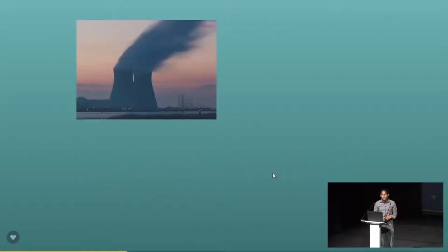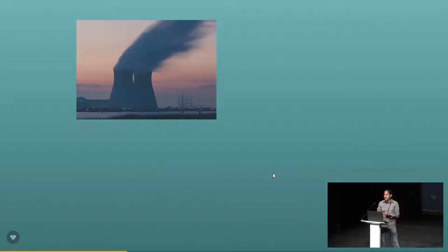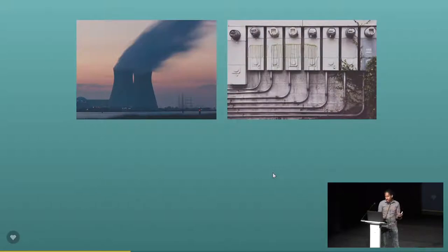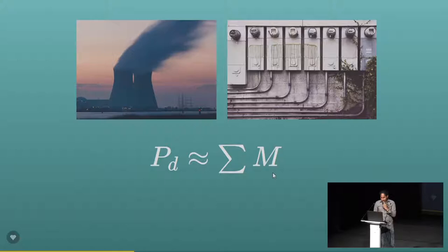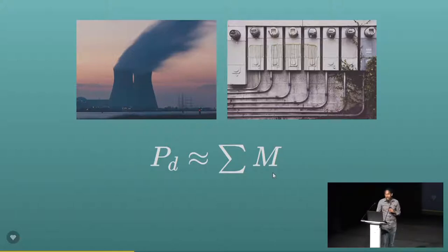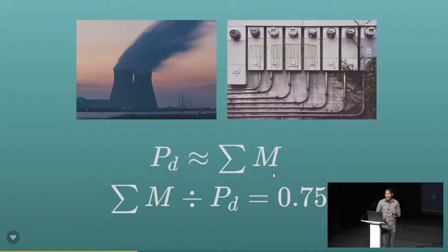So how do you quantify the theft of electricity? Well, you know how much power you're generating at the power plant, and you know how many meters you have or customer meters and customer locations. So basically, you add up the number of the consumption data. You compare it to the production data, and it should be approximately equal, right? No more than, say, 2% off. In Jamaica, we were finding that we were losing about a quarter of the power was being stolen. So that was money down the drain, or I guess, a wire.